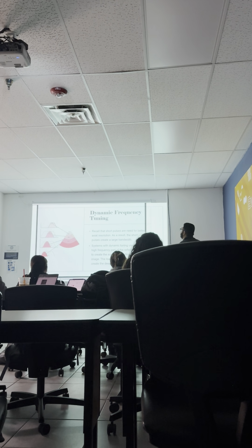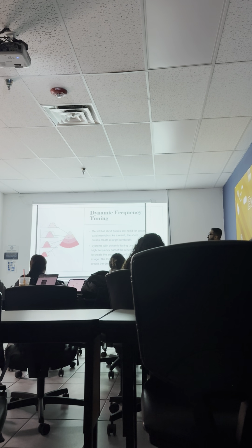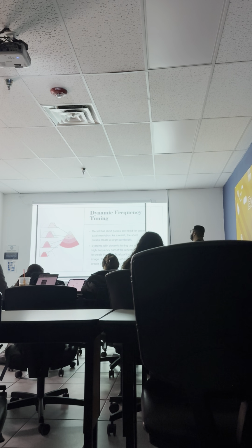Okay? So for dynamic frequency tuning, recall that short pulses are needed for better axial resolution. As a result, the short pulses create a large bandwidth. And what creates the short pulses? The backing material, okay? Systems with dynamic tuning use only the high frequency part of the reflected pulse to create the superficial portion of the image. The lower frequencies are used to create the deeper portion of the image.